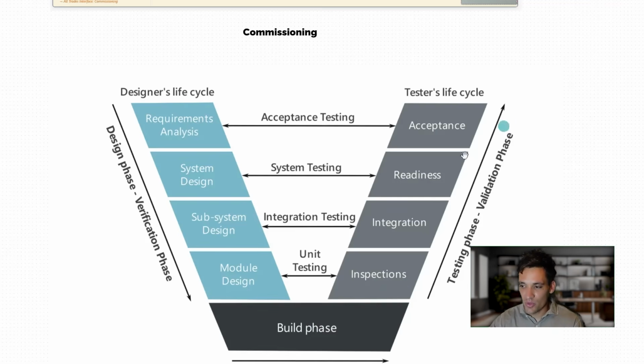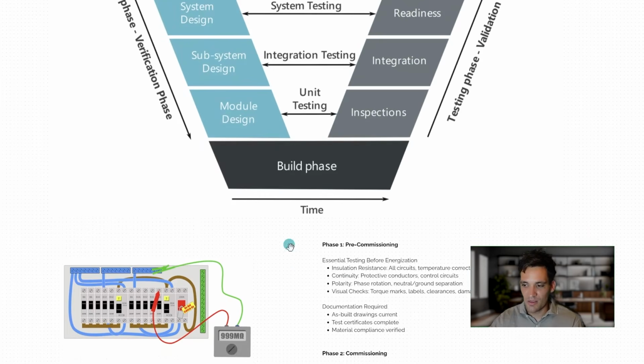Commissioning is then all of these stages of the process where we're validating that the design, the way it's been installed, fulfills the requirements. So the end stage of commissioning isn't testing that cable A goes to cable B. It's testing that the room meets the lighting requirements. We're testing the initial requirements to ensure they've been fulfilled.